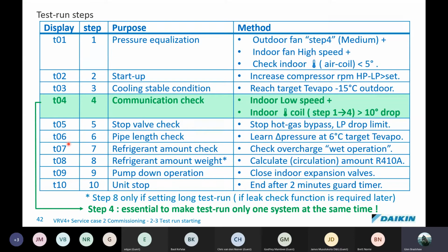And this is the critical part that we are interested in. This is where we can start to do testing of whether the units are performing, okay, as designed. All right, and on heat recovery machines, we will do 1 or 2 mixed tests, but we cannot always do all the units. If you've got 20 odd units, we cannot do a combination of all of them to see whether you've got swap piping and cables coming off your BS boxes. So we'll do 1 or 2.